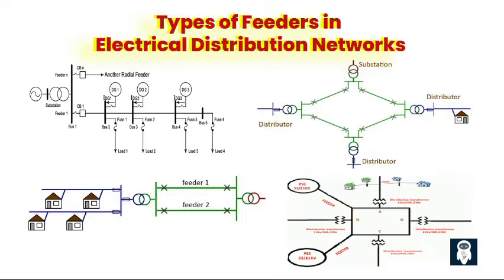Second, the ring main feeder forms a closed-loop configuration where power can flow in both directions. It provides redundancy and reliability in the distribution network. If a fault occurs in one section, power can flow through the other direction, ensuring uninterrupted supply to the connected loads. Ring main feeders are commonly used in urban areas and critical infrastructure where continuous power supply is essential.